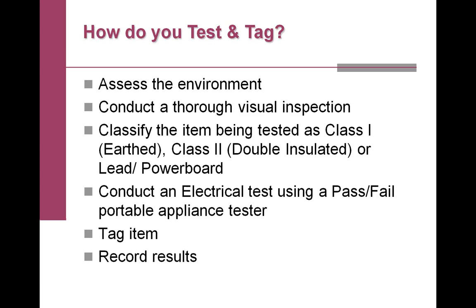Once the workplace assessment dictates the test frequency, the next step is to assess the items under test. This involves a visual inspection, looking for a number of things we train people to check, and classifying the type of appliance. Essentially, 99% of portable appliances tested in the workplace are either Class 1, an earthed appliance with a protective earth circuit, or Class 2, double insulated, meaning no earthing system. Most handheld appliances these days are double insulated. I won't get too technical with the electrical theory, but it's a straightforward process to classify them. Other items include leads, such as extension leads, power boards, or IEC leads, which most computers and monitors have as an exchangeable lead at the back.